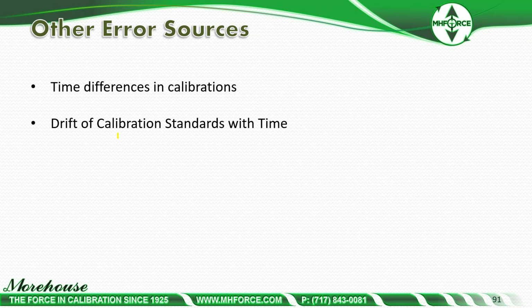Our weights are timed, that it waits 3 seconds between application of weights. So you put one weight on, wait another 3 seconds. So if I'm putting 10 weights on, it's going to be 30 seconds until the force is fully applied. And then once the force is fully applied, we're going to wait 30 seconds until we start taking force points. There is a difference. If we would wait 6 seconds versus 30, there is a difference.